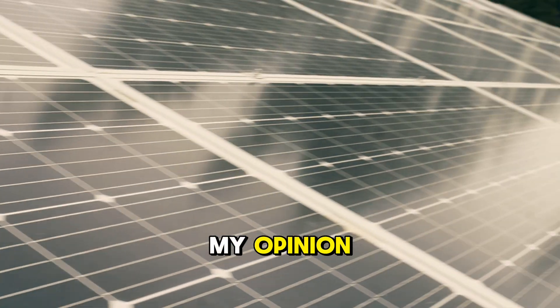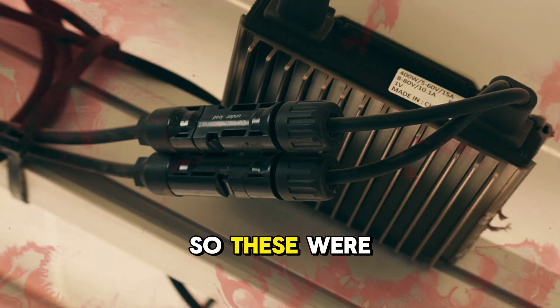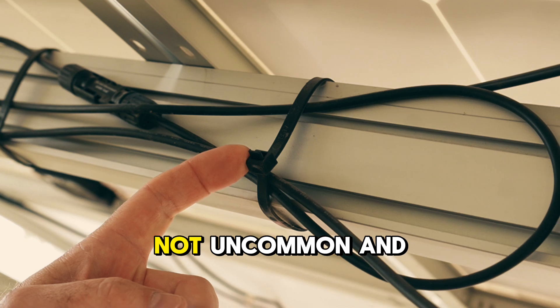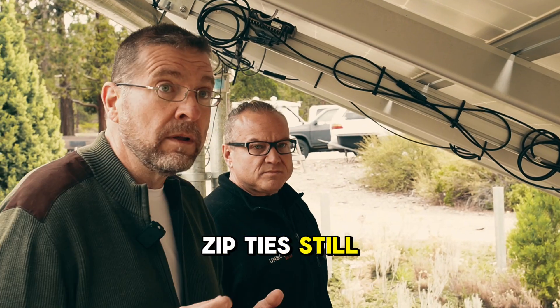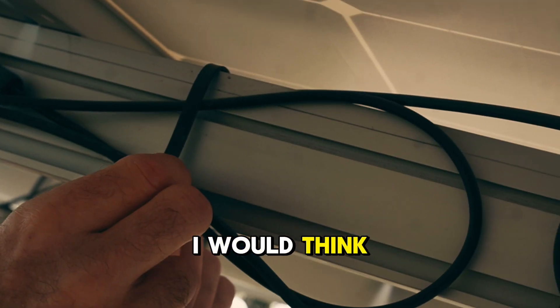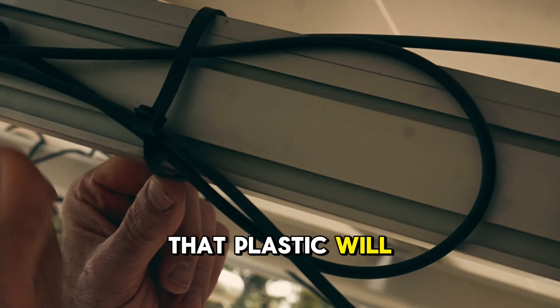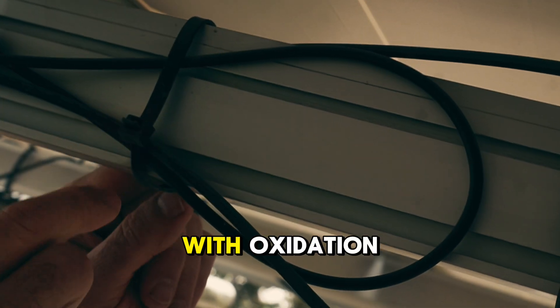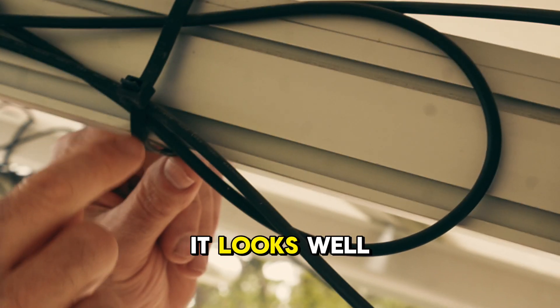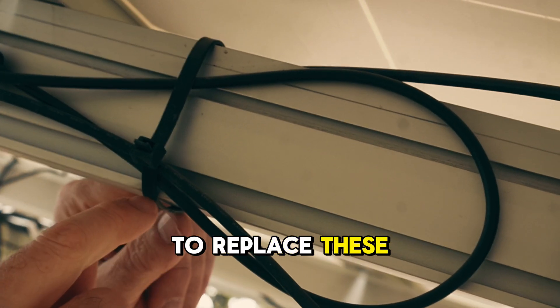This system — in my opinion cable management was done sufficiently well. These were done with good old-fashioned zip ties, and that is not uncommon, and these zip ties still look to be in pretty good condition. These don't seem like they're cracking in any way yet. Though if you were to unzip one of these, that plastic will have that hard bend — that's what happens with oxidation. You could snap it. It looks well done and it can be maintained over the years if you need to replace these ties.